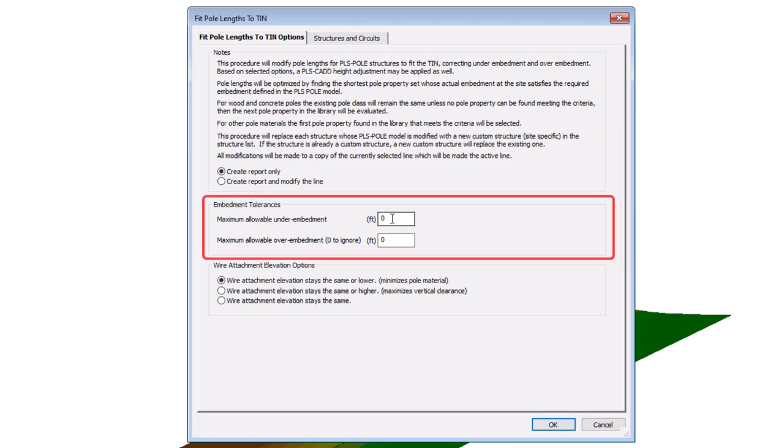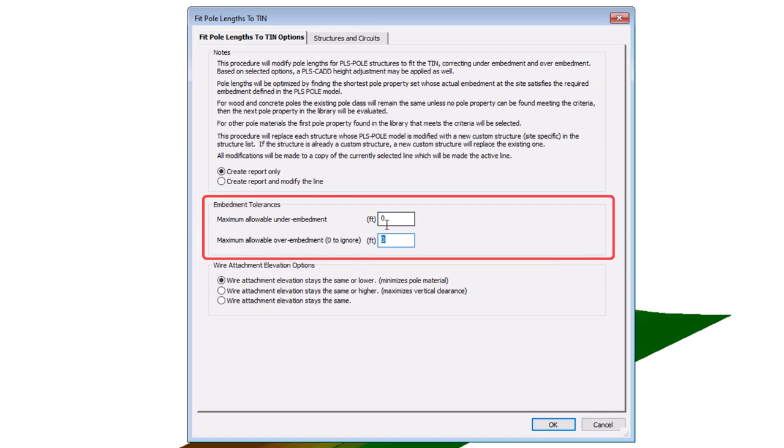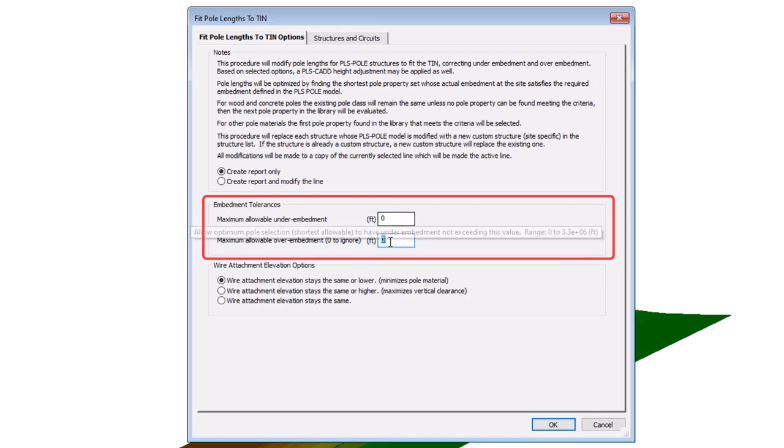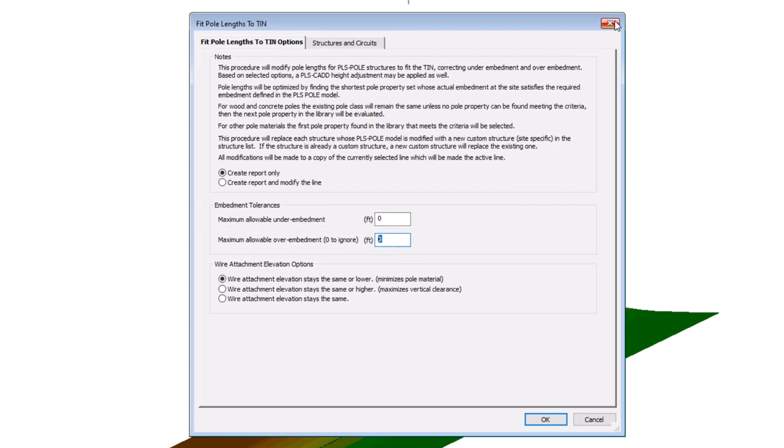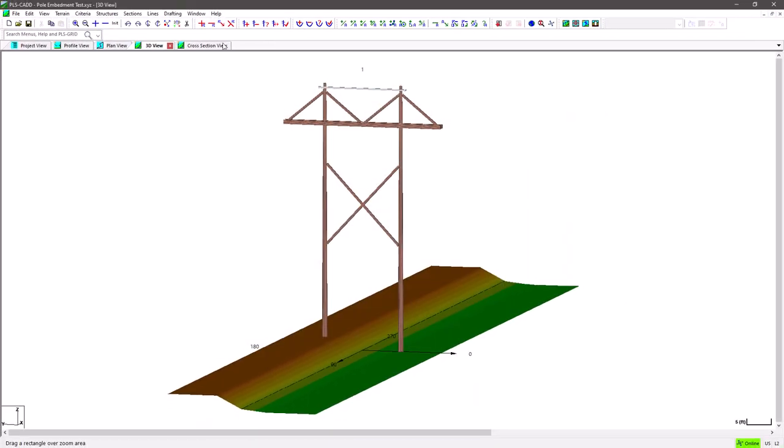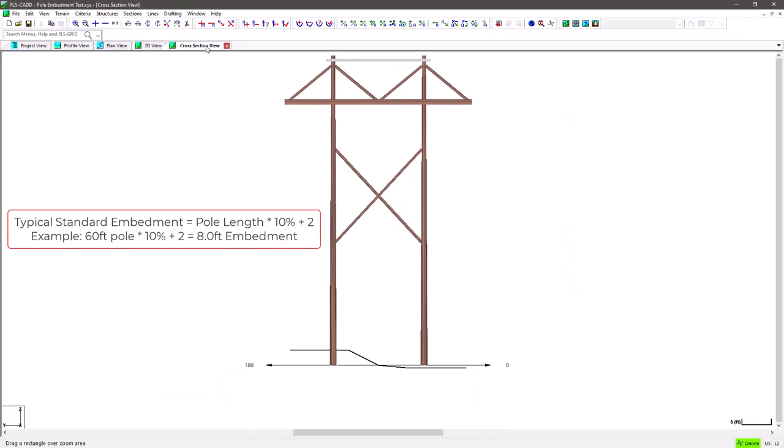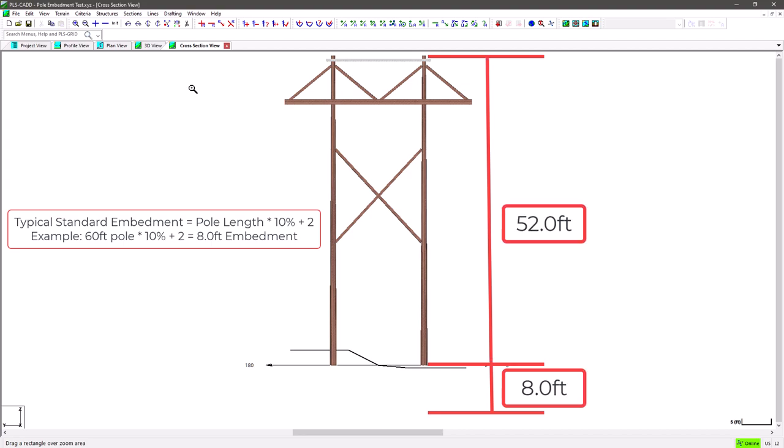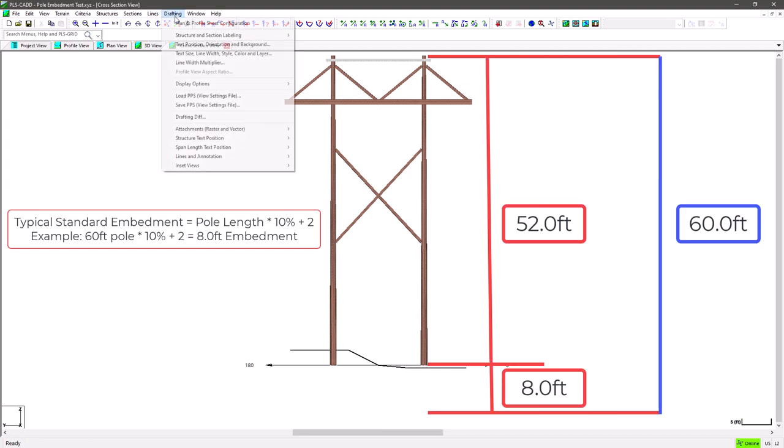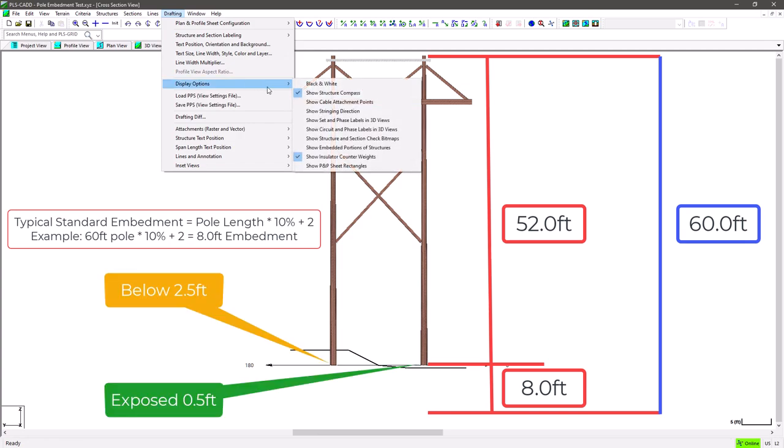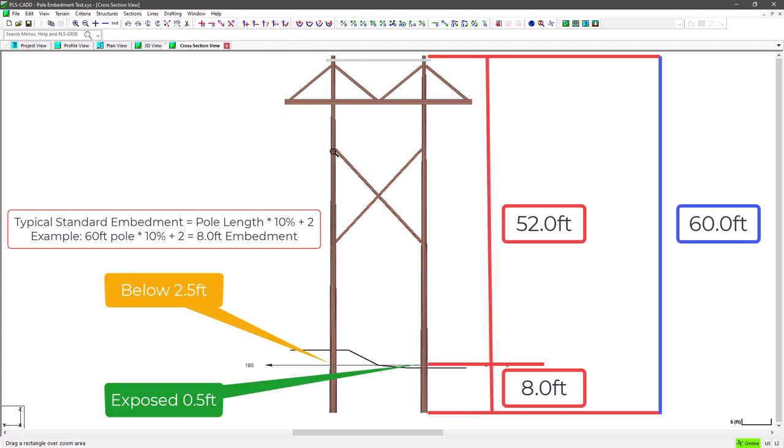The next setting allows you to define the thresholds for maximum amounts of over and under embedments. A typical default most folks use for embedment is 10% plus 2, where you take 10% of the pole length and add 2 feet to arrive at your standard embedment. If we look at the structure in this example model, you will see how both of these poles are using the standard 10% plus 2 embedment, and are all at the same elevation leading to one pole being exposed above the tin surface and the other that extends below the ground.